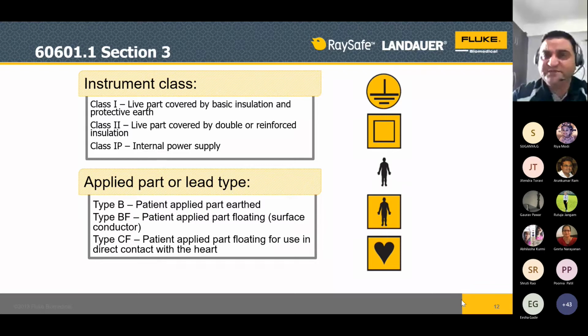Suppose I am talking about class 2: live parts covered by double or reinforced insulation. Why are we using double insulation? Why not single? We use double because we want minimum leakages and shocks from the equipment. If the first insulation fails, we still have the second to protect. Equipment is sometimes like that. Then class IP is internal power supply. Analyzers, machines, electrosurgical units used in hospitals, you can say that is a typical example of class IP.